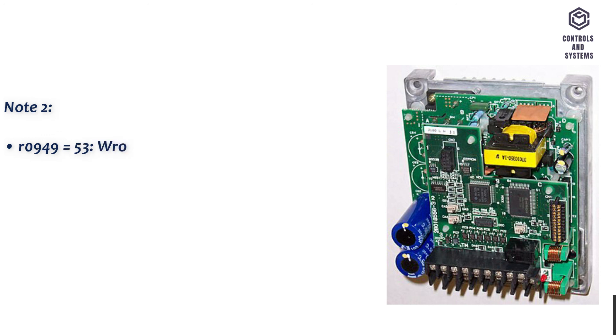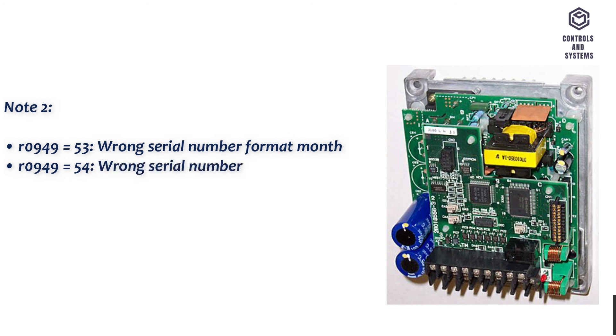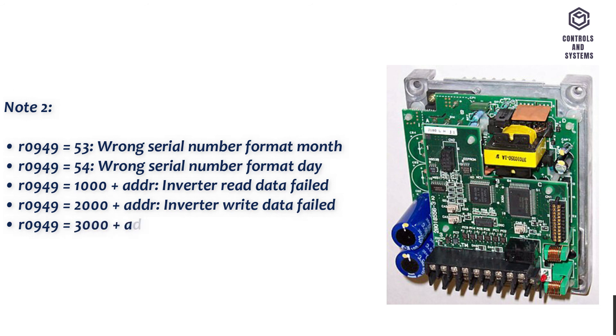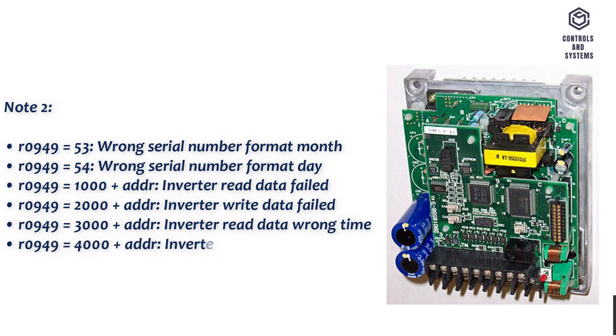R0949 equals 53: wrong serial number format month. R0949 equals 54: wrong serial number format day. R0949 equals 1000 plus address: inverter read data failed. R0949 equals 2000 plus address: inverter write data failed. R0949 equals 3000 plus address: inverter read data wrong time.